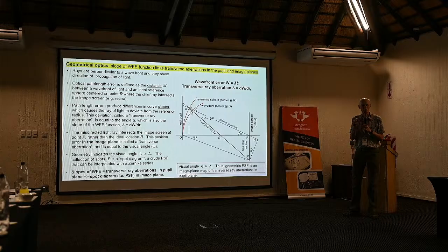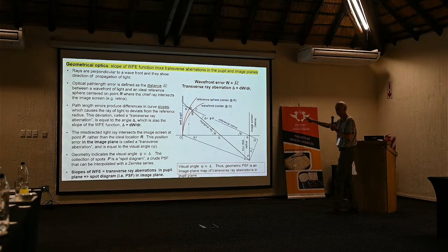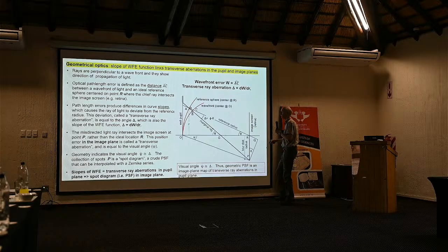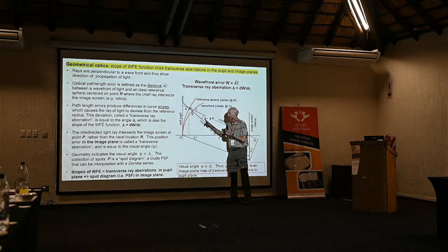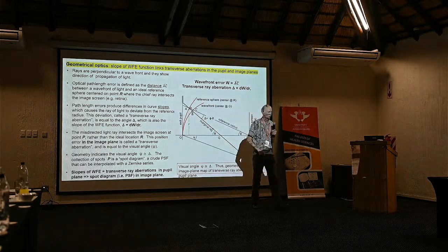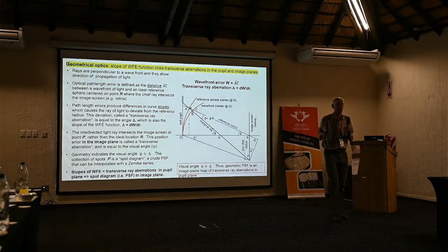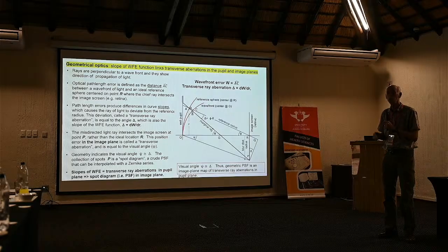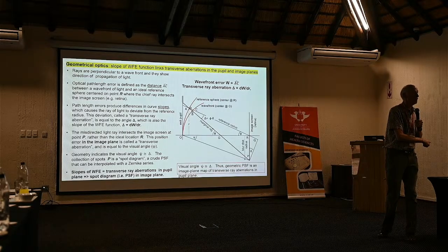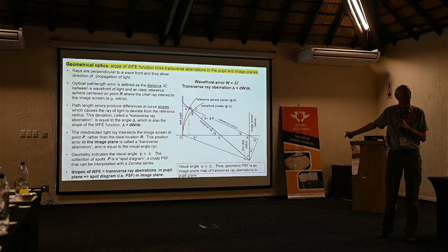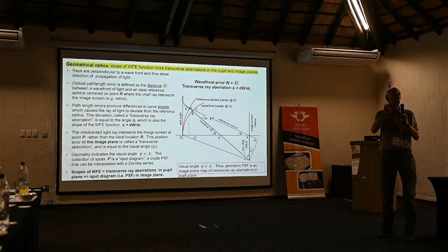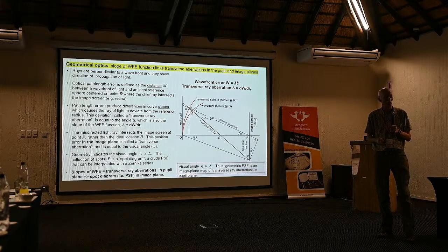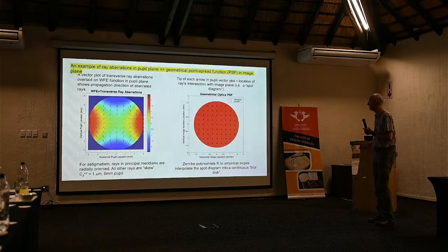I say almost because there's a small approximation you have to make when analyzing this geometry. But phi and delta are almost equal. And most times we just say they're equal. In fact, instruments are built that way, so that if you measure the wavefront slope, you know where the rays will hit in the retina. And so if you take lots and lots of points in the pupil, calculate all those slopes, find out where all those points are, and guess what you got? Something called a spot diagram.